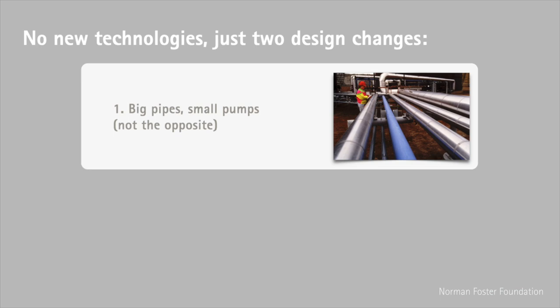A pumping system's pump, motor, inverters, electricals must all be big enough to overcome the friction. So their size and roughly their capital cost will fall as nearly the fifth power of pipe diameter. And yet the capital cost of the fatter pipe goes up as only about the second power of diameter. So when we optimize the pipe as a component, we're pessimizing the system.